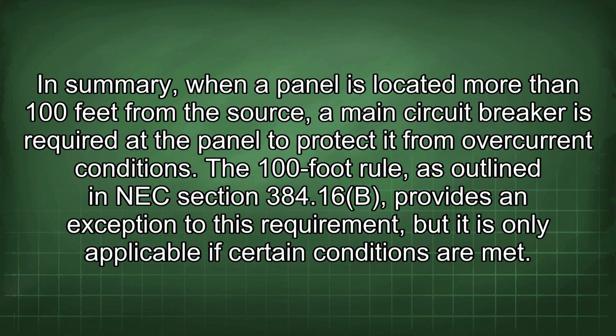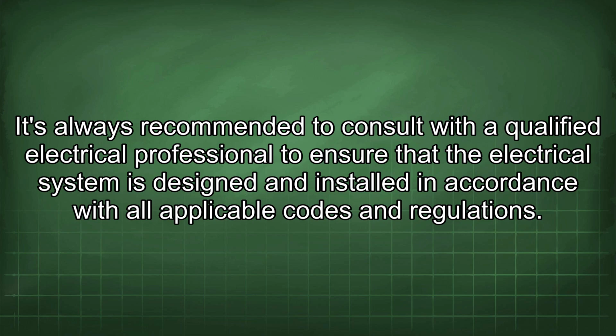regulations. In summary, when a panel is located more than 100 feet from the source, a main circuit breaker is required at the panel to protect it from overcurrent conditions. The 100-foot rule, as outlined in NEC Section 384.16b, provides an exception to this requirement, but it is only applicable if certain conditions are met. It's always recommended to consult with a qualified electrical professional to ensure that the electrical system is designed and installed in accordance with all applicable codes and regulations.